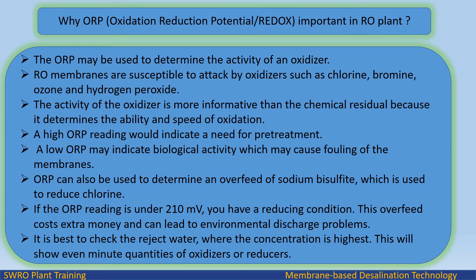Why is Oxidation Reduction Potential important in an RO plant? The ORP may be used to determine the activity of an oxidizer. RO membranes are susceptible to attack by oxidizers such as chlorine, bromine, ozone, and hydrogen peroxide. The activity of the oxidizer is more informative than the chemical residual because it determines the ability and speed of oxidation. A high ORP reading would indicate a need for pretreatment.